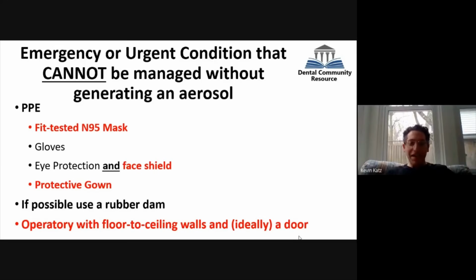Yeah, so it is a bit funny to have the "ideally a door." If you're arguing that you need floor-to-ceiling walls, I would assume it's because they're trying to create an environment in the operatory that is negative pressure to the hallway, potentially, or certainly, if it's not negative pressure, to try to create a separate environment in the operatory from the hallway. And so in these airborne diseases, or diseases that, based on the precautionary principle, you're trying to treat as an airborne disease, generally what would be recommended is to have high numbers of air exchanges in the room. And then the second piece would be to create a negative pressure between the operatory and the hallway.